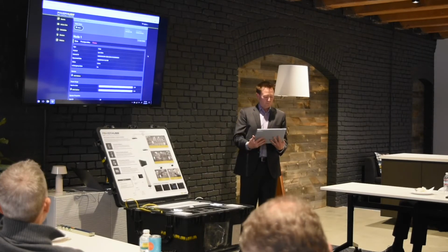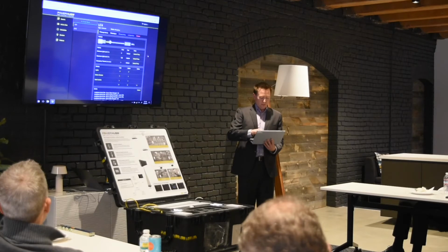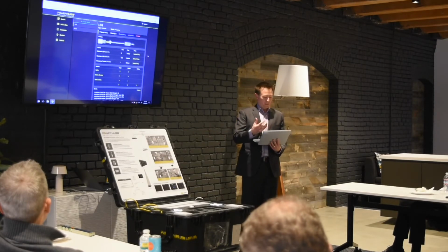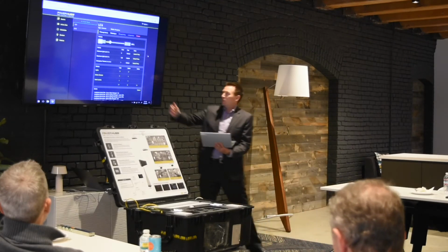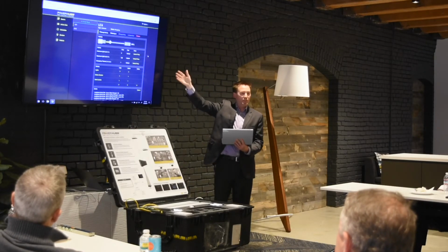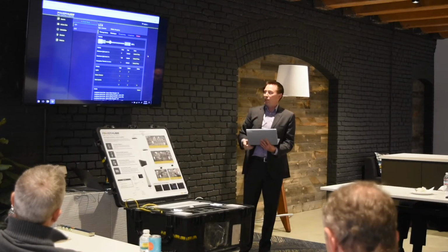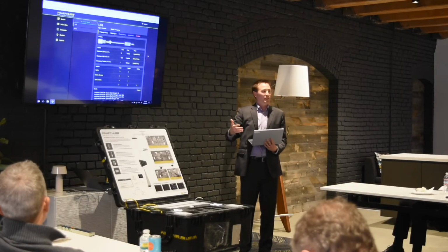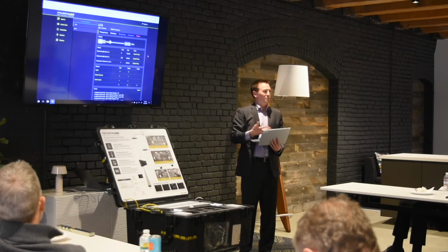If I go back to action sets, actually if I go to spaces again, it's all about just associating things to each other, or to a space, and then that acts as a container, and then we have policies that you set, and based on those policies, you can either do it at the space level or space type. Let's say all hallways operate this way, or you could even do it at the individual light. But those policies really dictate how it behaves, and by doing those two things, just associating things and setting policies, it's that simple.